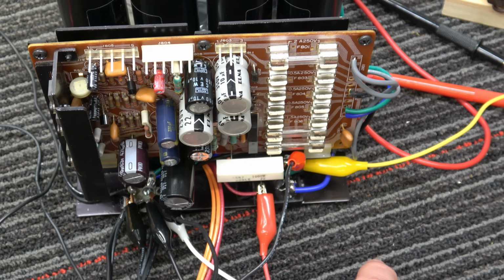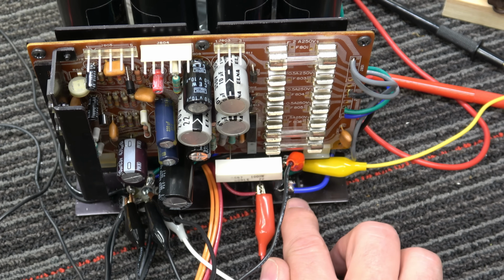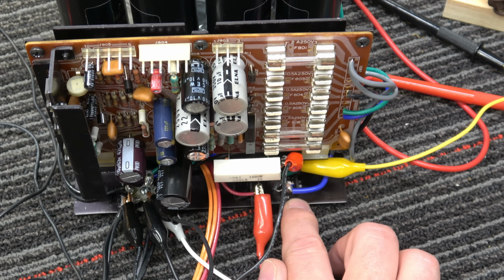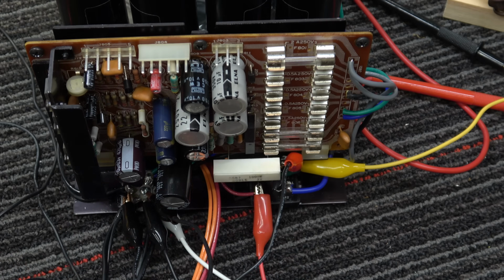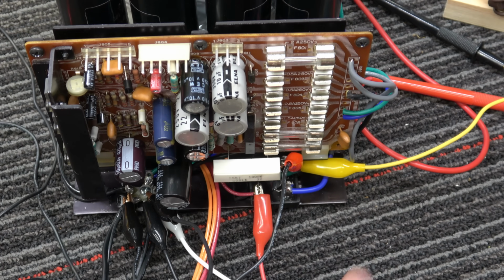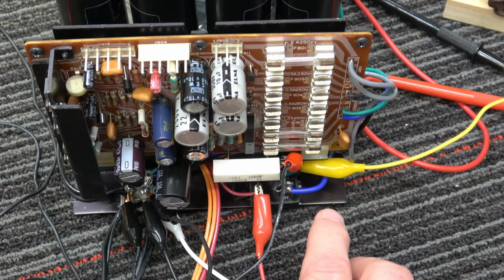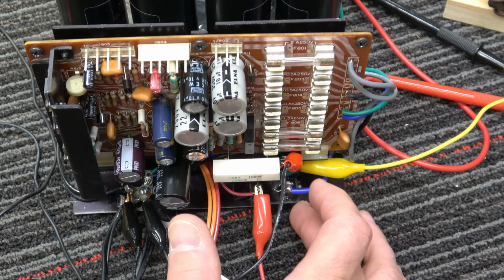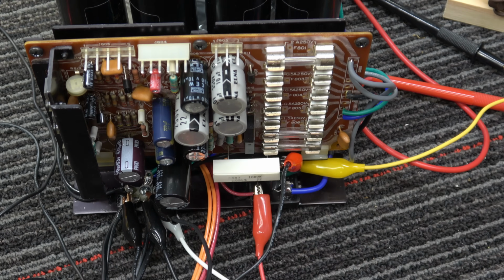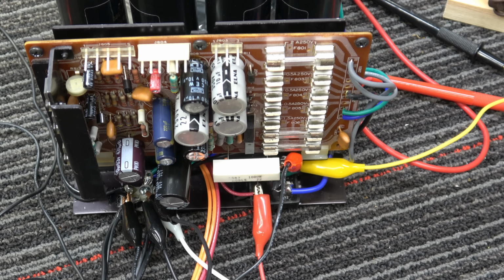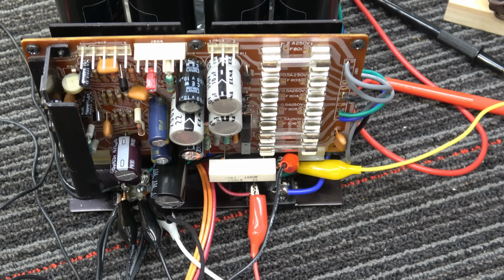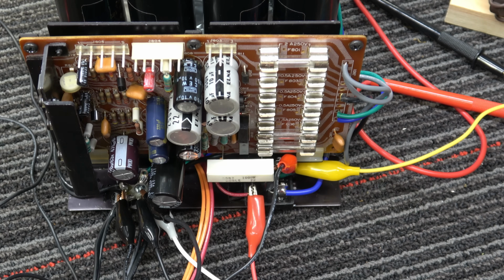Now, I think we may even be exceeding that for a split second when it goes to charge the capacitors up initially. So you're still going to need a soft start circuit, and even if it could handle that, it would be so hard on your incoming line that you could pop your circuit breaker in the house. So we're still going to put a soft start circuit in there.